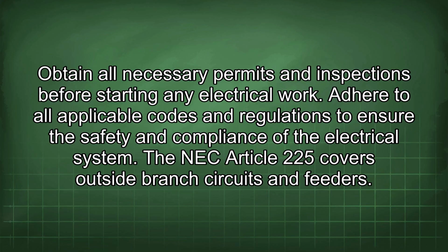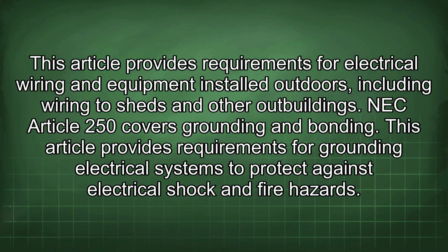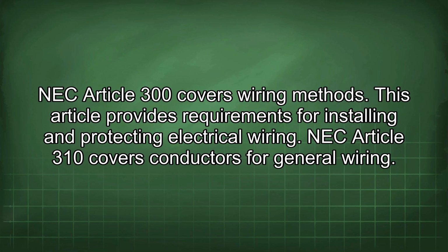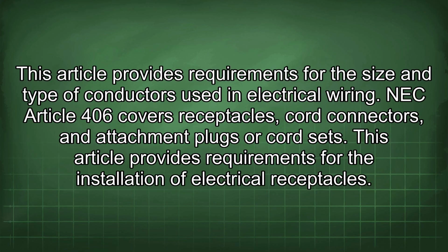The NEC Article 225 covers outside branch circuits and feeders. This article provides requirements for electrical wiring and equipment installed outdoors, including wiring to sheds and other outbuildings. NEC Article 250 covers grounding and bonding. This article provides requirements for grounding electrical systems to protect against electrical shock and fire hazards. NEC Article 300 covers wiring methods. This article provides requirements for installing and protecting electrical wiring. NEC Article 310 covers conductors for general wiring. This article provides requirements for the size and type of conductors used in electrical wiring.